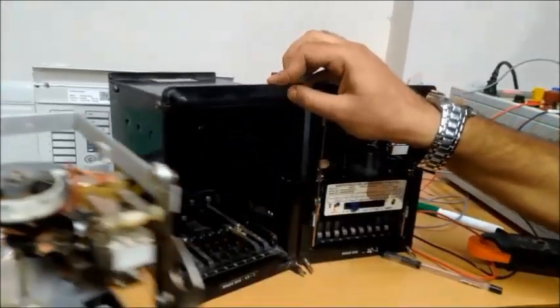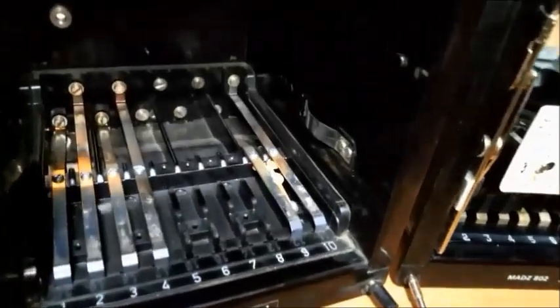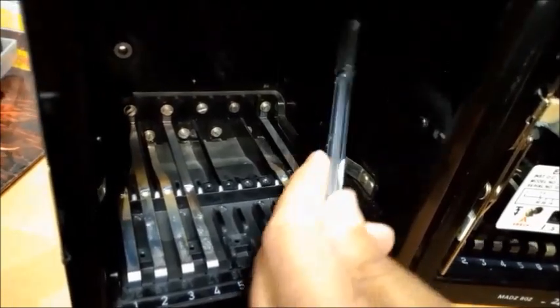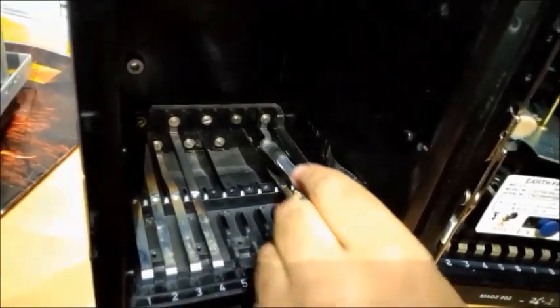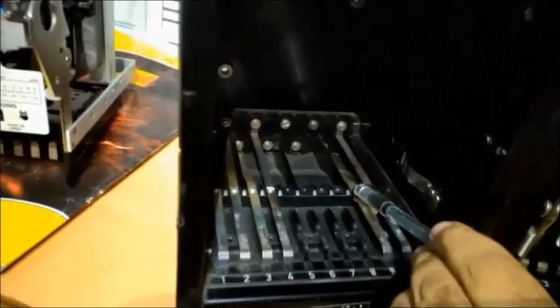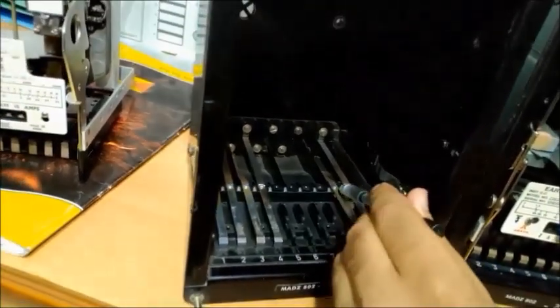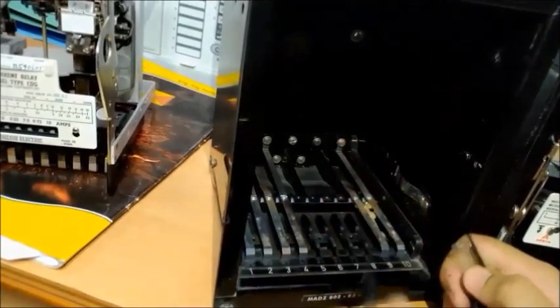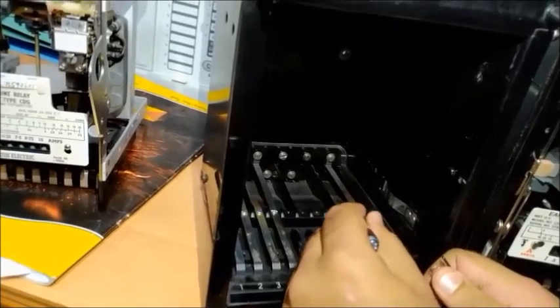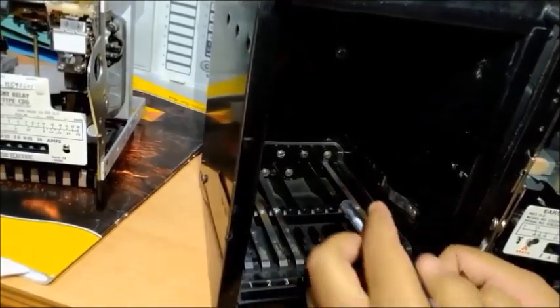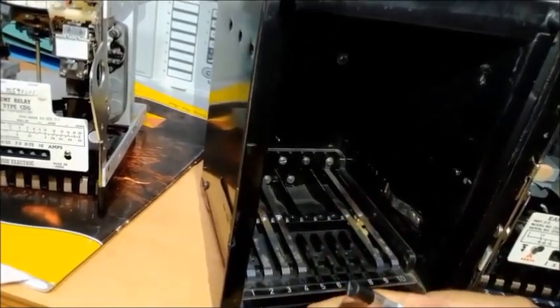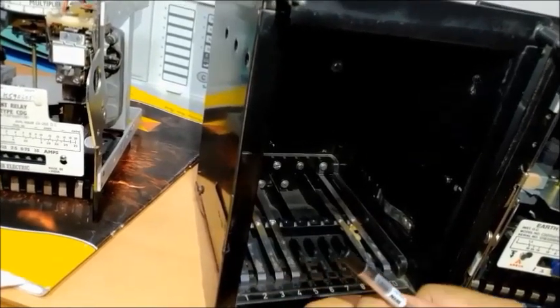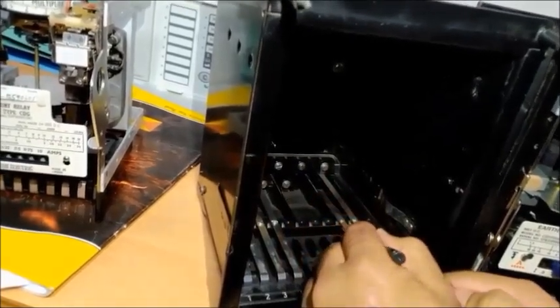I just show you one thing. See. When we remove this relay, there is a this side is 910. That is connected to your field. That is CT secondary. Current will come. So if this is open, so heavy voltage is generated here. So that is our interlock. When we remove the relay parts, so this is directly shorted. Because CT secondary is never open. We have to always short. So now we are going to inject our pickup current.